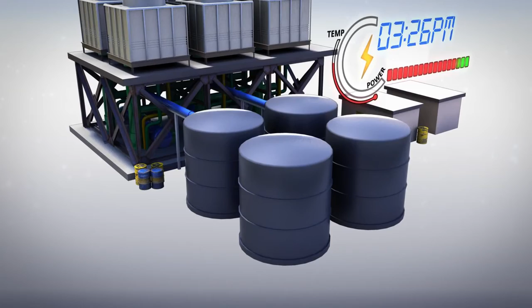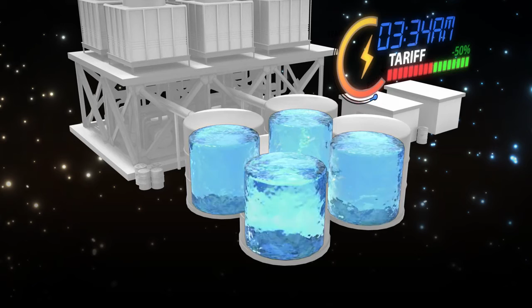In order to achieve a far more efficient system, KJ Group is able to incorporate a thermal energy storage system into the DCS, storing cooling energy during night time when the energy cost is low and discharging the energy when the energy cost is high.